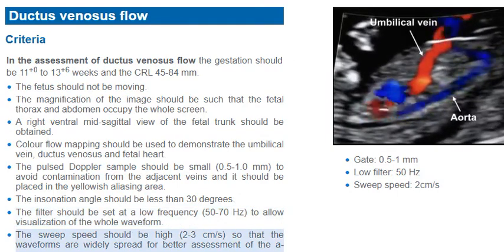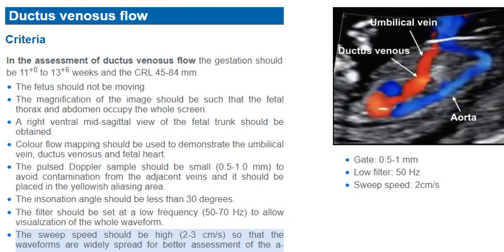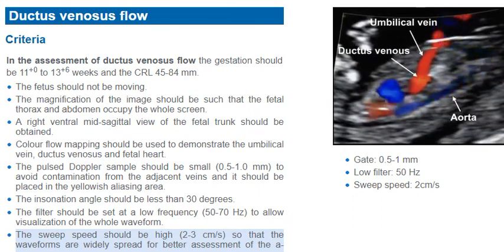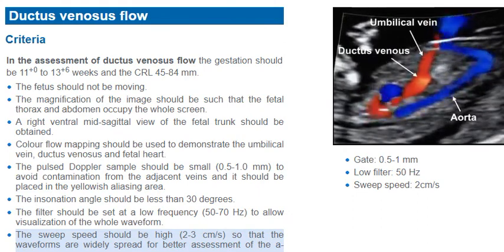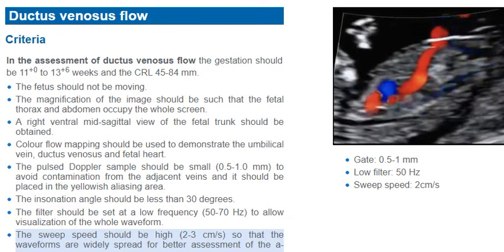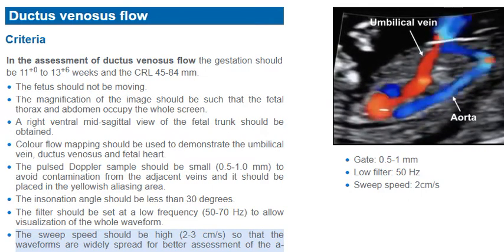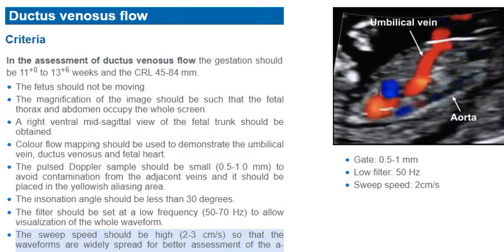The sweep speed should be high, between 2 and 3 cm per second, so that the waveforms are widely spread for better assessment of the A wave.